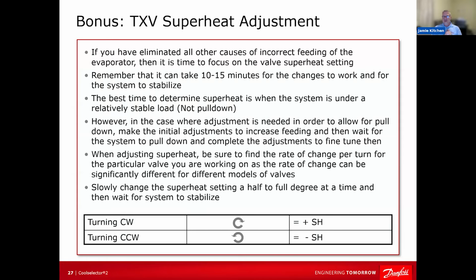I do know in the early days of the pulse width modulated valves, the EVs, they're like a solenoid valve that opens and closes. Okay. And the amount of time it's open compared to the amount of time it's closed over a given period of time determines your capacity. They can create a pressure wave in the refrigerant line. And if you put your dryer too close sometimes, that pressure wave can cause the connection to crack. But those are old valve styles, and they've largely been replaced with the ones that don't pulse as much. But that was something we learned the hard way, right?